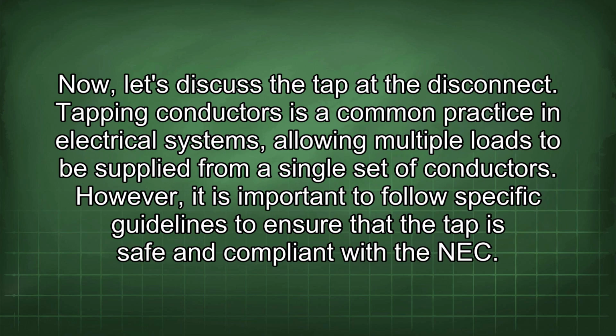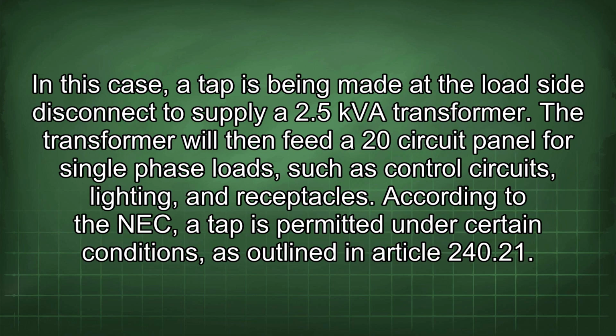Now let's discuss the tap at the disconnect. Tapping conductors is a common practice in electrical systems, allowing multiple loads to be supplied from a single set of conductors. However, it is important to follow specific guidelines to ensure that the tap is safe and compliant with the NEC. In this case, a tap is being made at the load side disconnect to supply a 2.5 kVA transformer. The transformer will then feed a 20-circuit panel for single-phase loads such as control circuits, lighting, and receptacles.